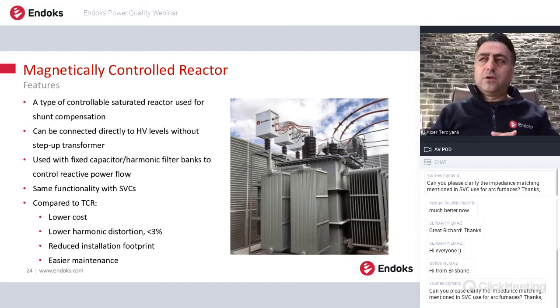It is very good for voltage regulation, reactive power support, because unlike SVC, actually, the conventional thyristor controlled reactor, this solution is very compact and needs low footprint, and also not so much complicated control system. And an important thing is that there is no need for any cooling system. In conventional SVCs, you need a very big and powerful cooling system. But here, the MCR, you don't need any cooling system. The control system is very simple, and it is very compact.